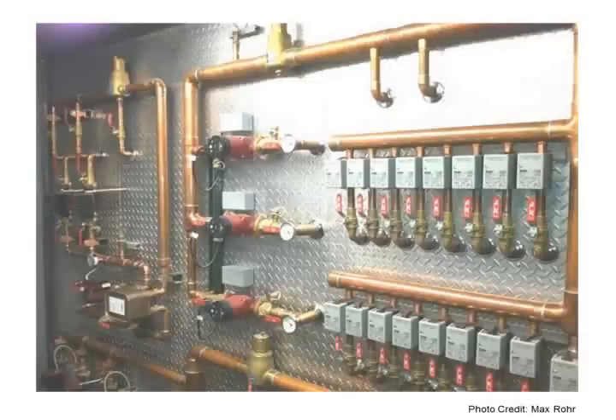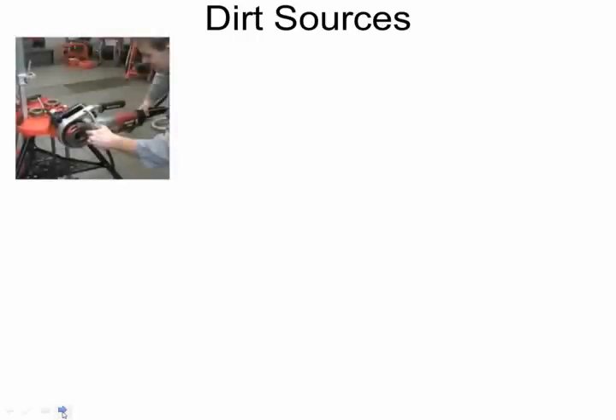Okay, what about those? They're excellent for reducing the energy cost of sending heat from A to B in a system. But what are some precautions as it relates to ferrous oxide and some of that very fine dirt that can get into a system or basically get created in a system as a result of corrosion? So we're going to start with, of the three topics, dirt, air, and pump conflict, dirt, and discuss, well, first of all, where does dirt come from?